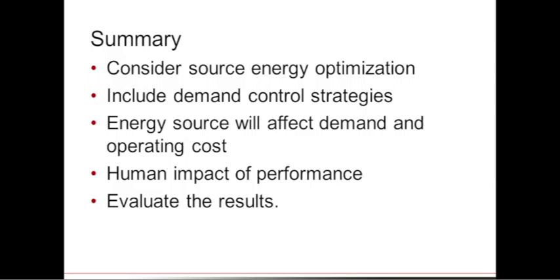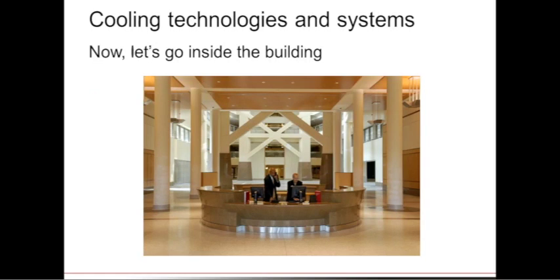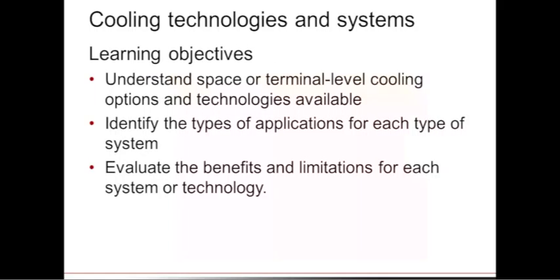To reduce energy costs and minimize source energy with fuel flexibility and electric demand avoidance, consider multiple fuel sources such as combining gas-fired and electric chillers to attack demand peaks. Demand control sequences in both equipment selection and operation are critical. Thermal and ice storage are increasingly viable at smaller scales for demand management. Operators and building occupants must be trained on demand performance strategies, and results should be continuously evaluated to ensure buildings perform as designed.